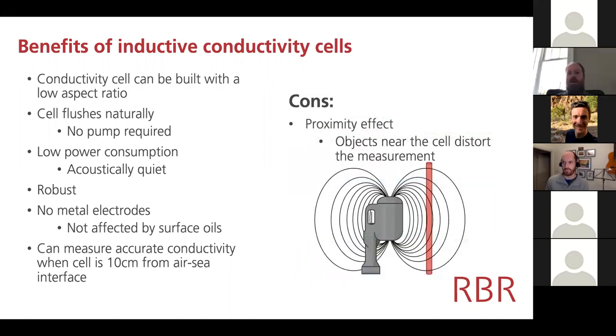Now, the major downside of an inductive cell is the so-called proximity effect. And that is that we are inducing a current into the seawater, and you can think of it really as a field. Although this current wants to take the shortest route possible to complete the loop, which means that it's dominated by field lines which are close to the cell, there are field lines which extend out actually to infinity. There's a practical limit on how far out those field lines really go, but clearly objects that are near the cell distort the measurement because a small fraction of the measurement is integrated over that space outside.